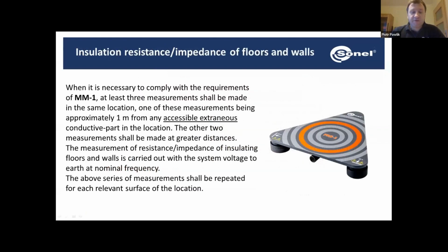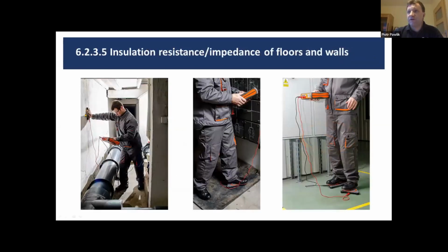All right, another measurement is the resistance of floors and walls. Here the standard defines what probe we need to use, and the rest is pretty much the same as other insulation resistance measurements. We're going to check the resistance between one point and another point of some insulation. We just need this special probe, so we can put it on walls or on the floors, like you can see over here. And we need to measure the resistance of walls in case we have some metal conduits, and walls and floors also in case of some special workplaces.